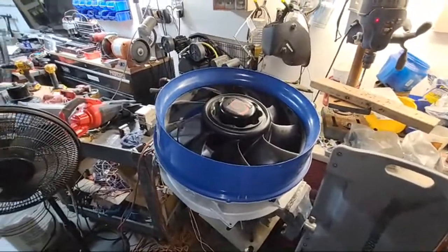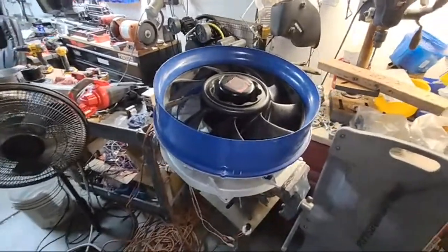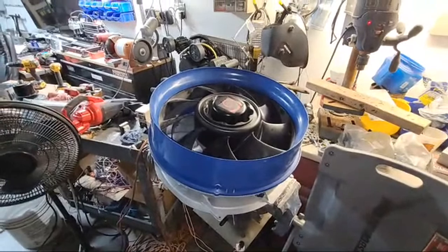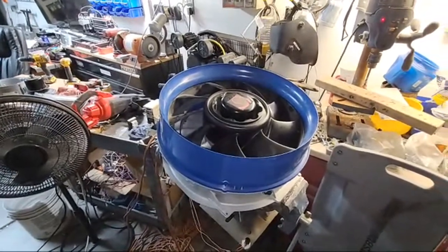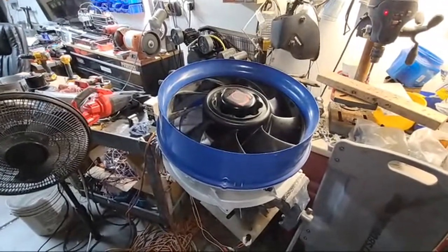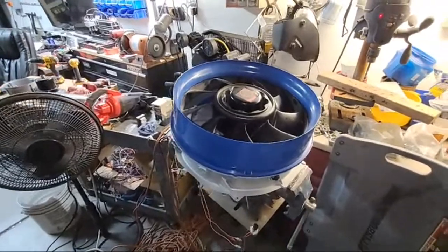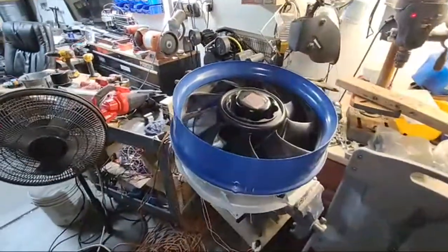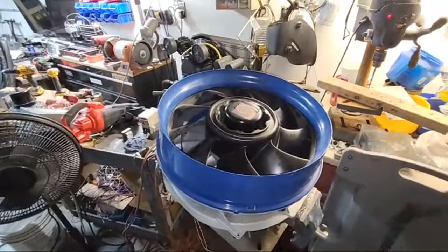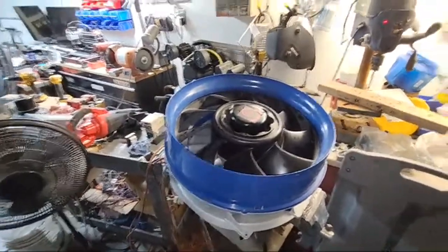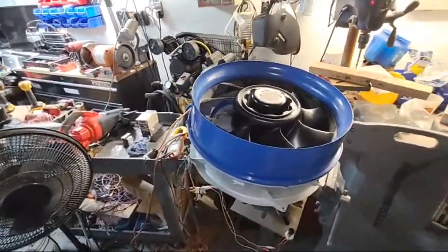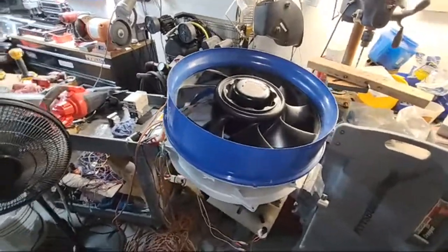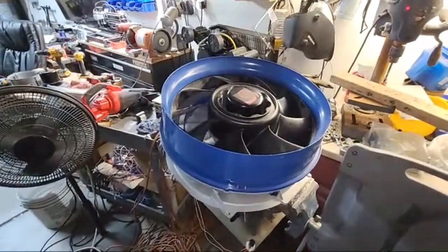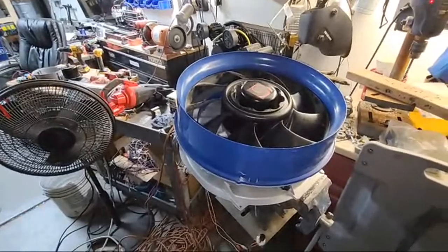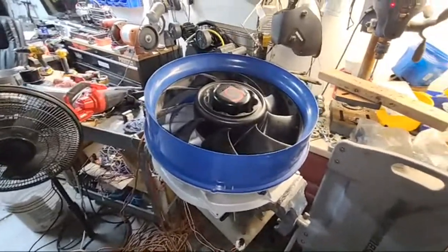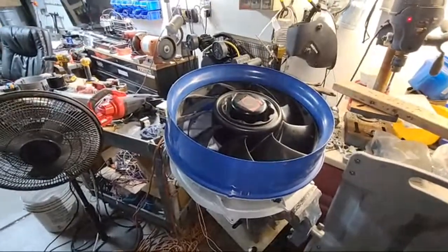I had to do that to 30 or more brand new water source heat pumps, the ones with the aluminum chassis, the 3.5, 4 ton units, with the water temperature fine and gallons per minute fine. You could put it in heat, and some of them did it in the winter, some in the summer. Those same units were tripping randomly. The guy would just reset it in his EMS system, but he would just get repeat trips on the same units. We went through part of a summer and then through a winter trying to figure it out.